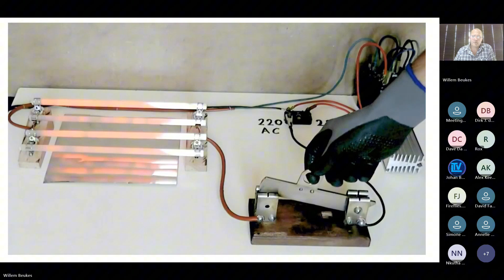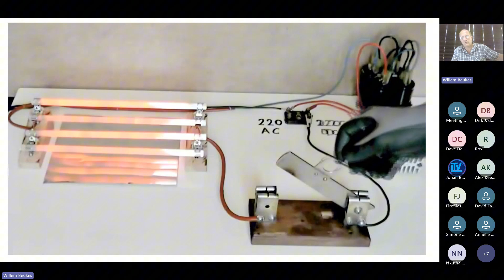Now here is AC, and the load you will see on the left-hand side will increase on the resistance tubes, and underneath the load, the gap separation will be increased to see if there's any arc forming between the gap separation. You will see a small contact spark there, and then it will stop due to the alternating current that's flowing through the system on 220 volt. So there's not a big arc forming, but when you change that over to DC voltage, you will see the separation arc is quite big, happening underneath load.